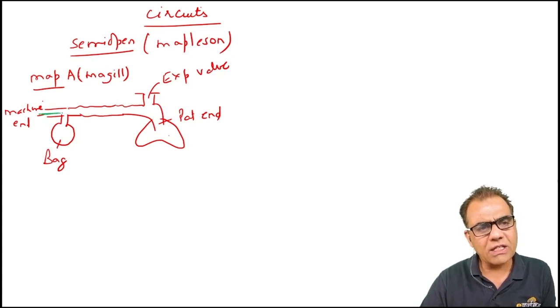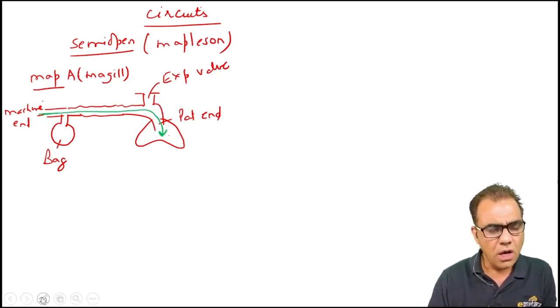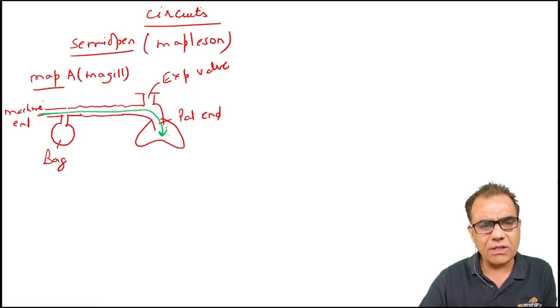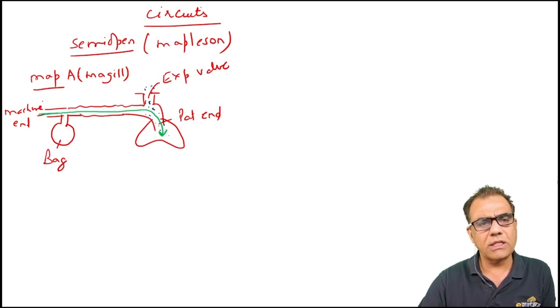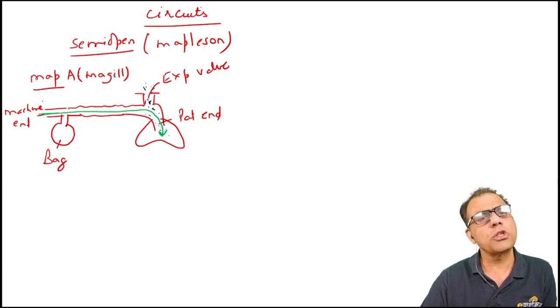So fresh gases coming from the anesthesia machine will be delivered to the patient, no doubt. Now the expiratory gases, which I am drawing here as blue dotted lines, most of these expiratory gases will go out into the atmosphere through this expiratory valve, but some of these gases will go back into the tubing. Now the gases which have gone back into the tubing will be re-inhaled by the patient. That is called rebreathing.